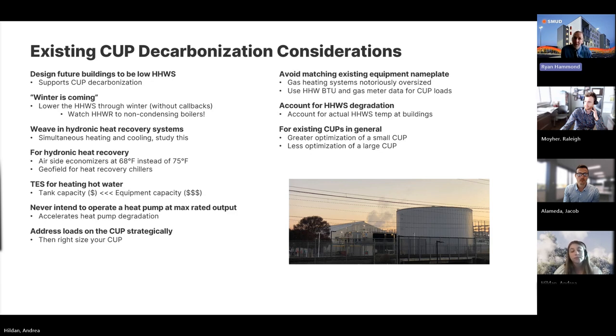Consider thermal energy storage for heating hot water. Trust me, tank capacity is a lot less expensive than equipment capacity. Very little maintenance, very little wearing out. Operational costs are negligible, just pump energy, and it's a wonderful way to go. Plus, to illustrate that, just concept-wise, if you had, say, 7 air-to-water heat pumps needed for a project, you could, in theory, trim that down to 3 with a thermal energy storage tank. And so you end up with fewer machines. Plus, they get to run at a sweet constant load instead of start-stop. As it was mentioned earlier, never intend to operate a heat pump at max rated output. It'll just burn it out and your electric bill won't be happy.